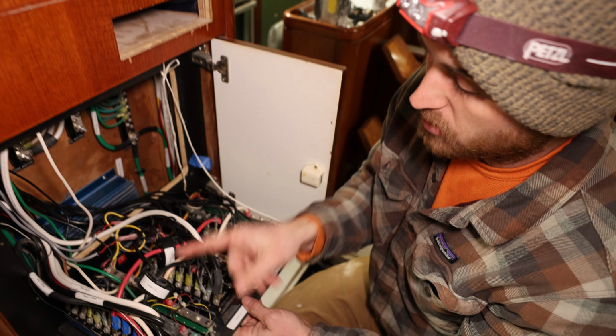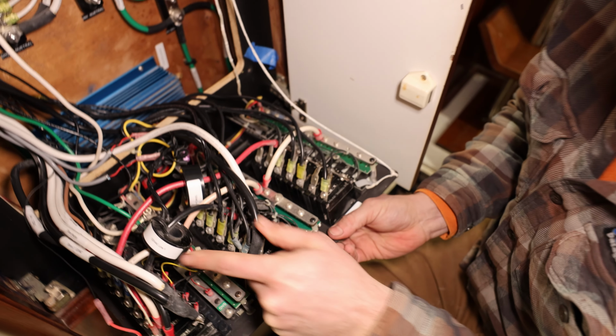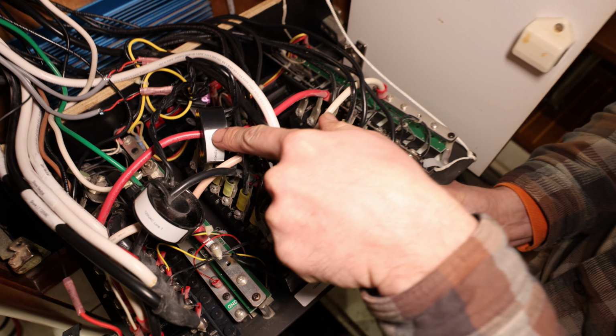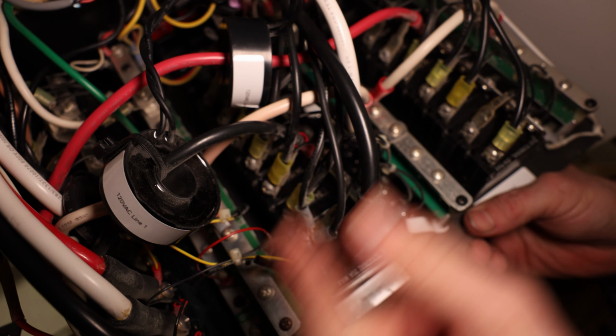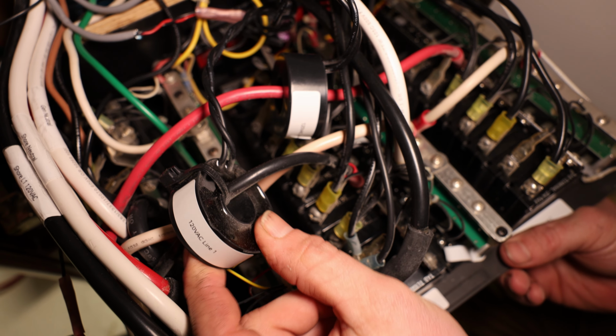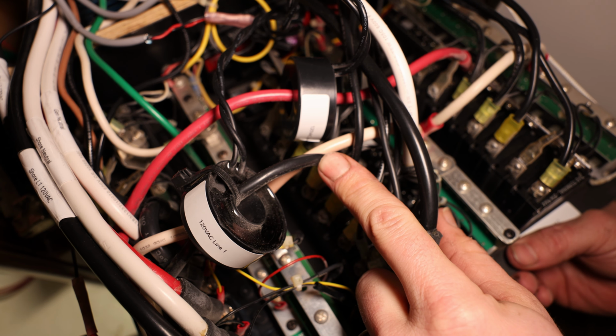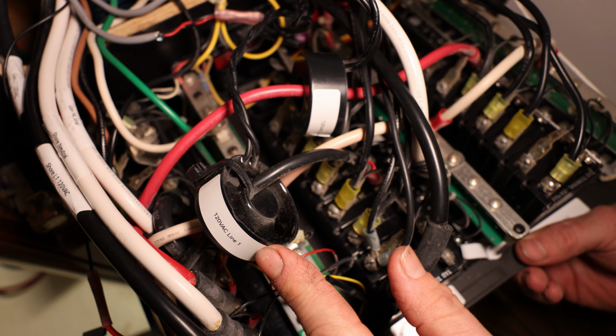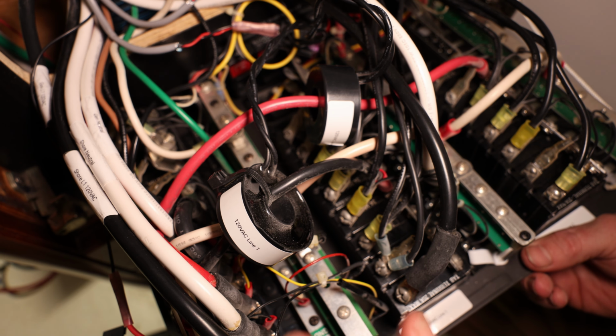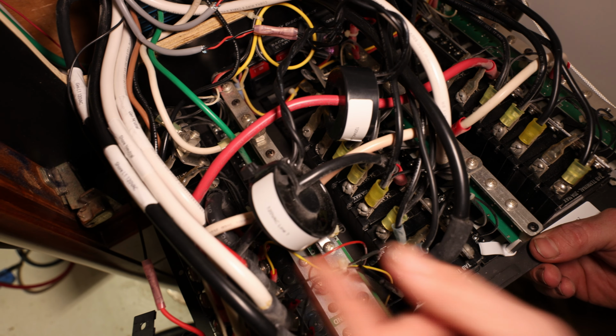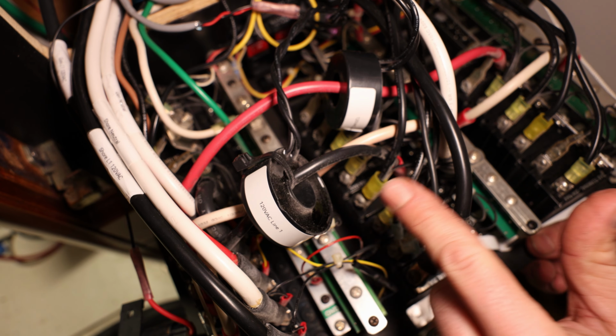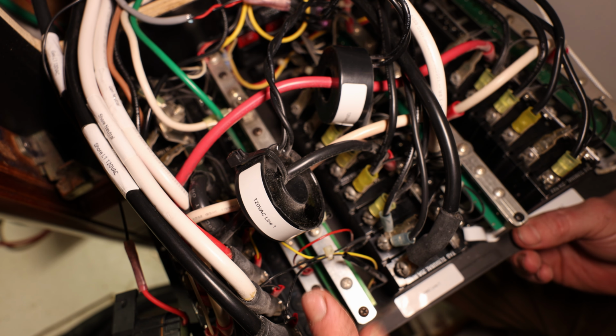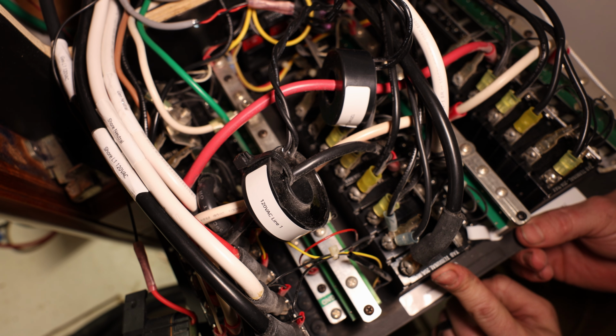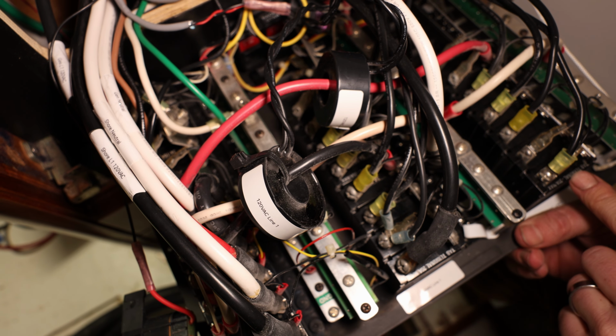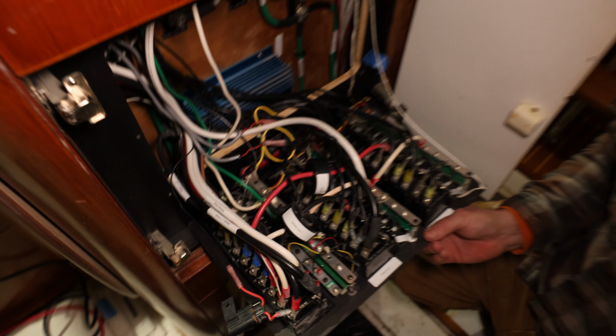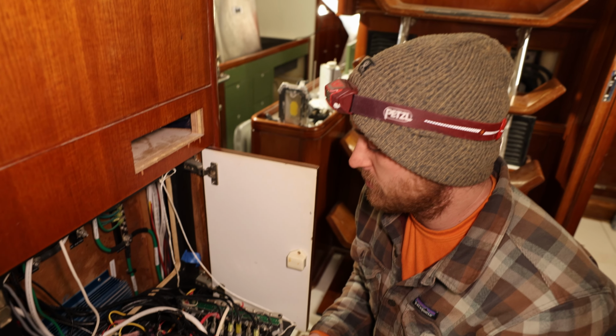These little donuts are also pretty cool, and I labeled these. These donuts are what feed the sensors on the main panel, measuring the amps running through each hot line. It's similar to using a voltmeter that clamps around a wire - it can read amps running through the wire without actually touching the conductors. This one reads the amperage going to line 1, this one reads line 2, and it displays it on our other panel telling us how much power we're using.